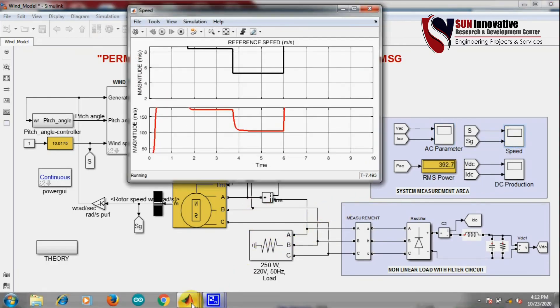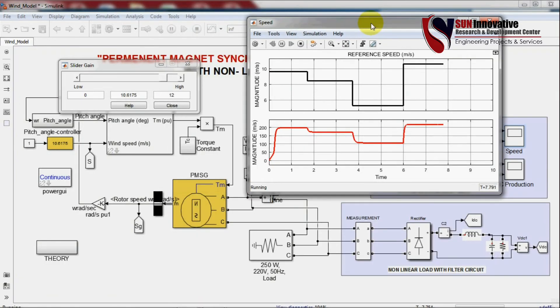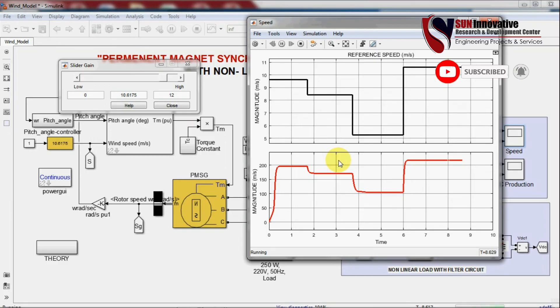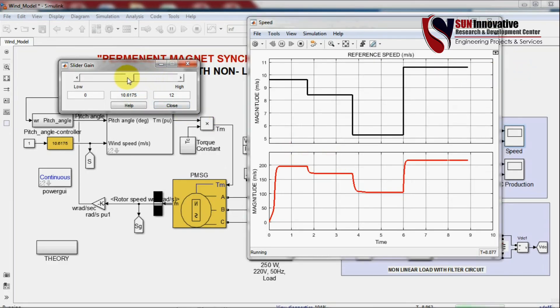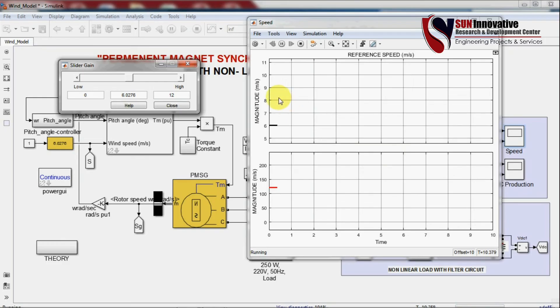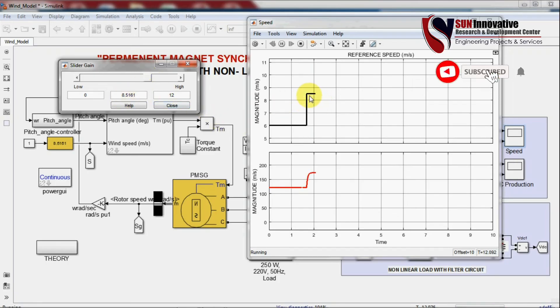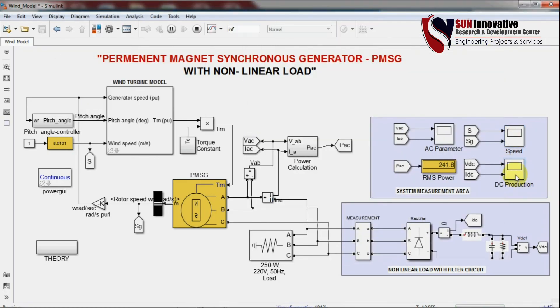Now the speed graph: the first graph is reference speed and the second is actual speed. When we change the speed reference, the generator should respond accordingly. Setting it to 6, the black line (reference) is at 6 and the red line (actual speed) changes immediately. Increasing to 8.5 for verification, the generator also responds immediately — confirming there is no delay in wind speed response, which is important to avoid generation losses.